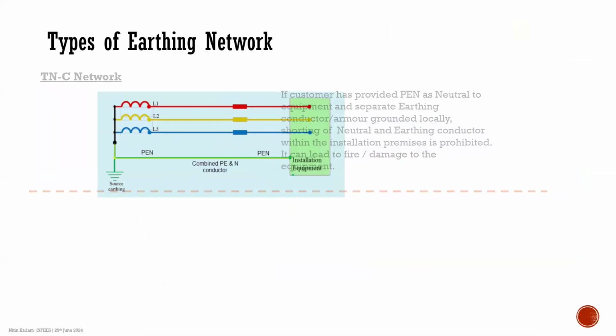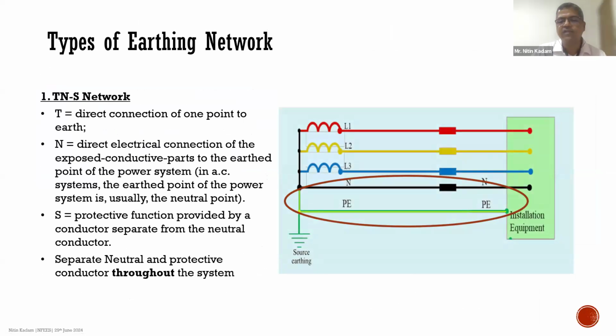So in case of a TN network, we'll have the MET somewhere here. All the earthing conductors in the building installation have to come from each installation to this MET. From the MET, they should be connected directly to the source earth. This is a metallic earth conductor available between the secondary of the transformer, the star point, and the MET terminal, and it helps you have a low value of earth fault loop impedance. This is also probably what Mr. Kiran Joshi was trying to ask. If this earthing is not properly connected, then the fault loop impedance test is not going to pass, because the fault loop impedance values will be higher than expected.